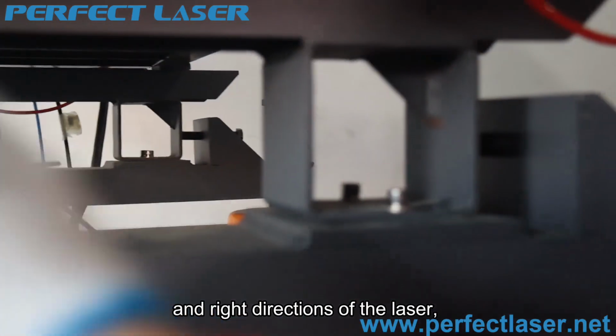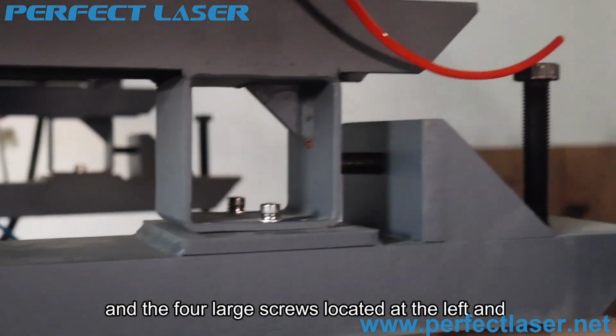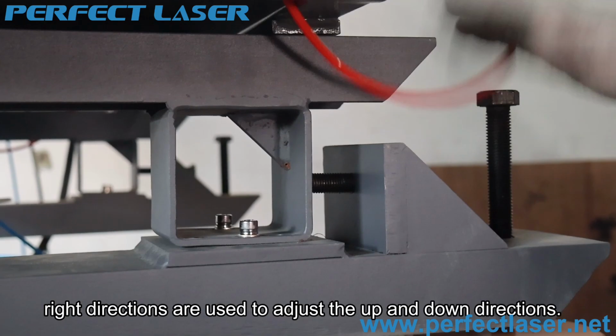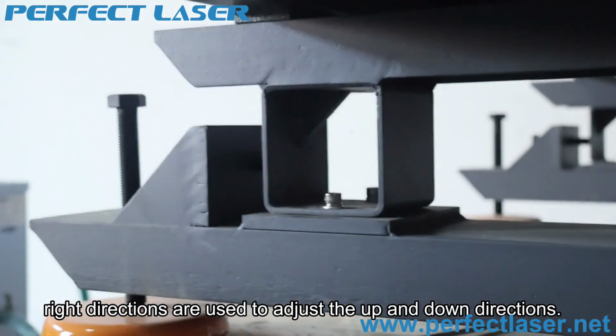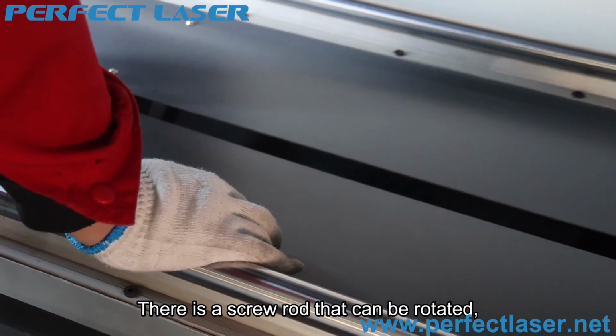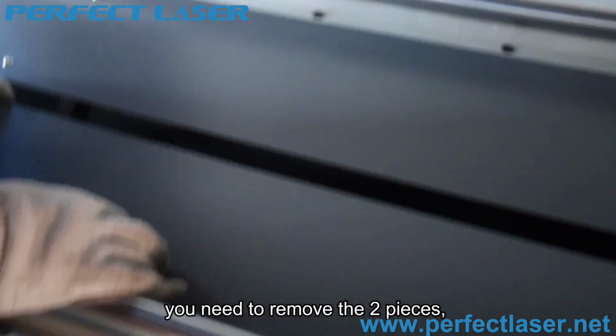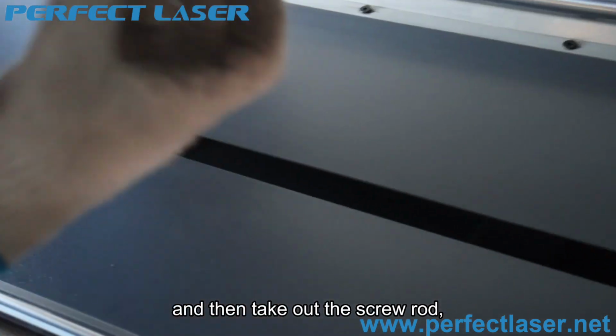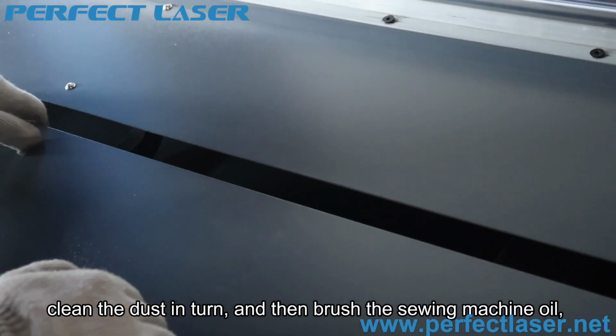and right directions of the laser, and the four large screws located at the left and right directions are used to adjust the up and down directions. There is a screw rod that can be rotated. You need to remove the two pieces, and then take out the screw rod, clean the dust in turn, and then brush the sewing machine oil, generally cleaning once a half month.